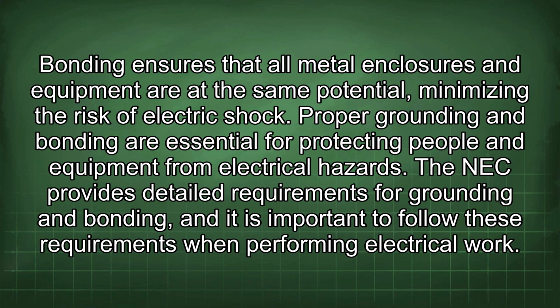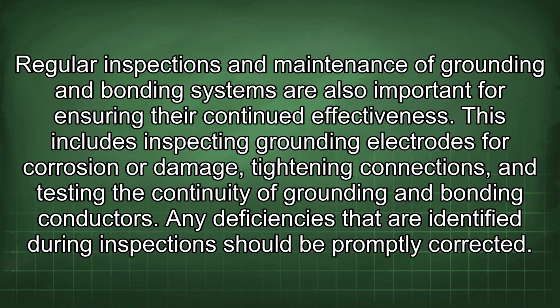The NEC provides detailed requirements for grounding and bonding, and it is important to follow these requirements when performing electrical work. Regular inspections and maintenance of grounding and bonding systems are also important for ensuring their continued effectiveness. This includes inspecting grounding electrodes for corrosion or damage, tightening connections, and testing the continuity of grounding and bonding conductors. Any deficiencies that are identified during inspection should be promptly corrected.